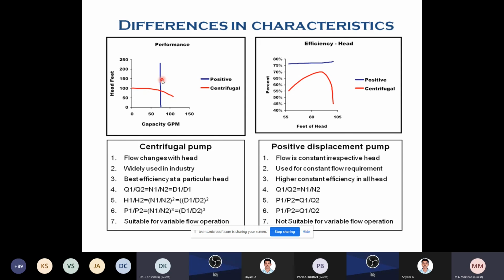For a positive displacement pump, the efficiency is very high, more or less the same all the time. But a centrifugal pump depends on the flow and on the head, so there is one maximum point, which is called the best operating point. In such a case, VFD is applicable, but not for the positive displacement pump. I have seen several energy auditing firms recommend VFD for positive displacement pumps. I asked them, for what? Whatever the flow, the head will not disturb it. The head will remain constant, the flow will remain constant, and there is no need for variation of the flow.